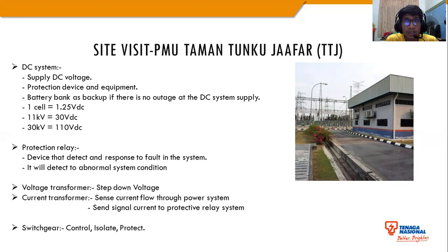The DC system is used to supply the DC voltage in the PMU, PPU, and CC components, such as switchgear, control panel, and relay activation. A protection relay is a device that detects and responds to system faults. It detects abnormal system conditions such as short circuit, over voltage, and reverse power flow.